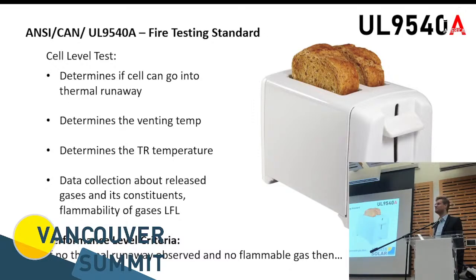Go ahead, Harsha. You mentioned UL 9540A is not a certificate. So if you can pass at least the most critical safety test here, what can you claim to be certified to? Exactly. So then you take that UL 9540A fire propagation test, and you said you passed the performance criteria on the cell level. And then you go to your certificate, as a manufacturer, of course, to your certification body, let's say CSA or UL, whoever that is.